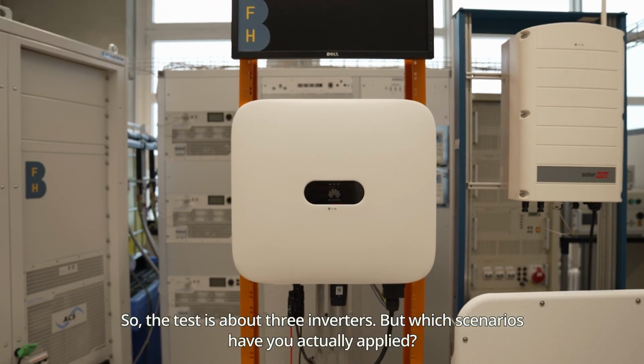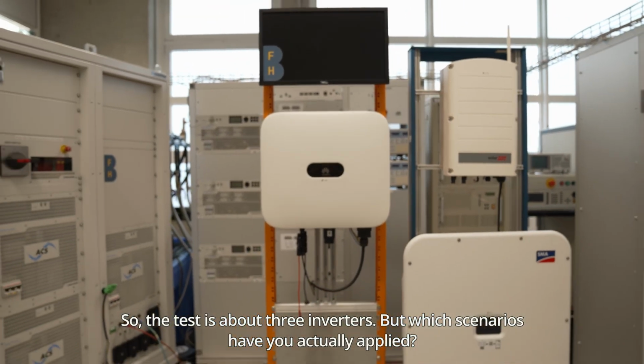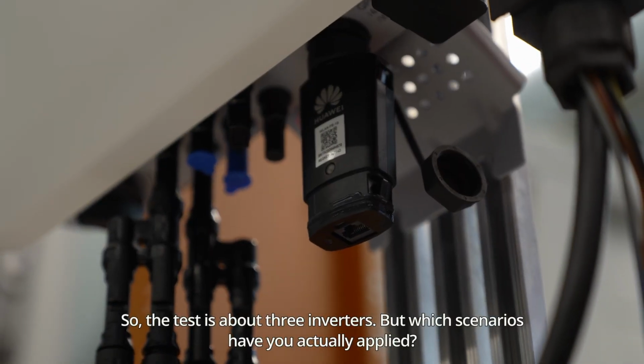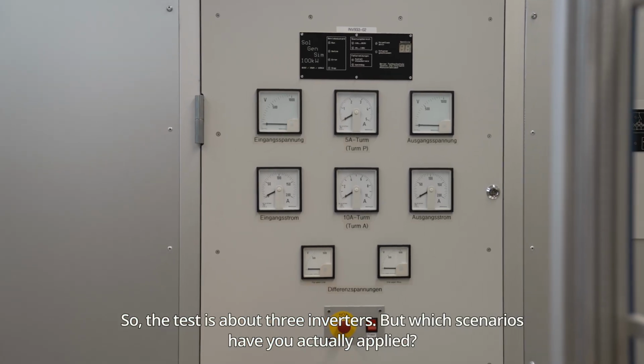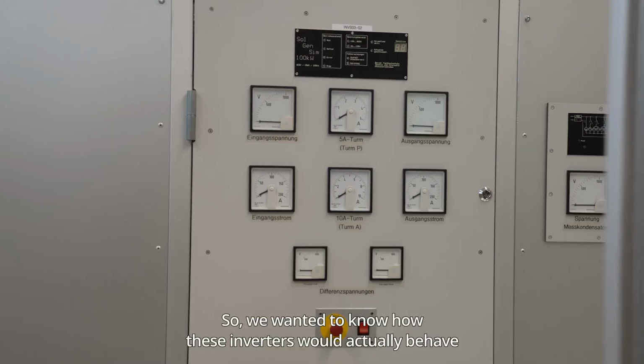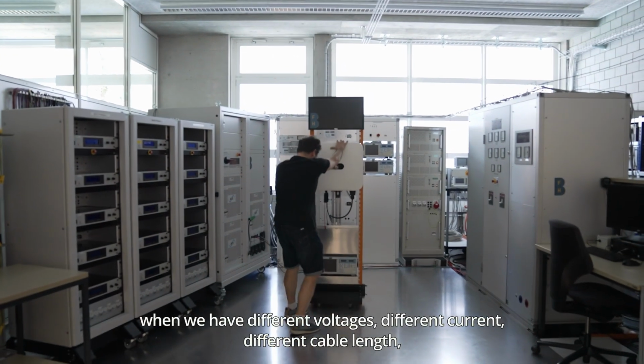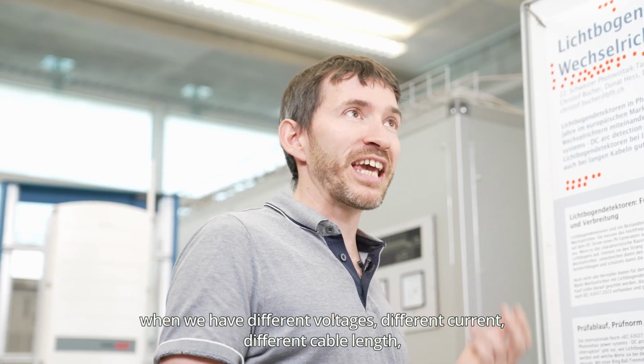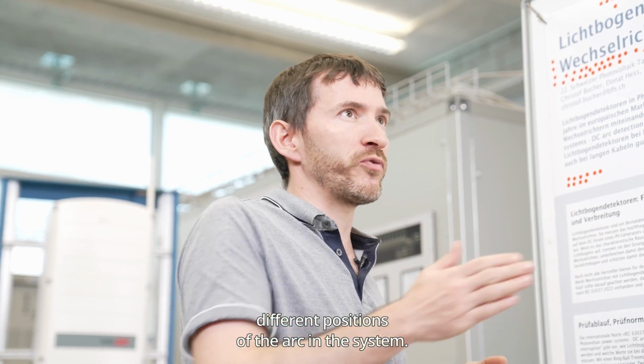So, the test is about 3 inverters. But which scenarios have you actually applied? So we wanted to know how these inverters would actually behave when we have different voltages, different currents, different cable lengths, different positions of the arc in the system.